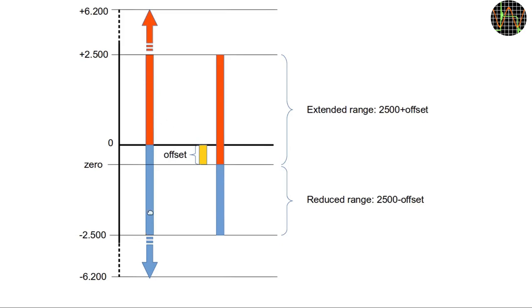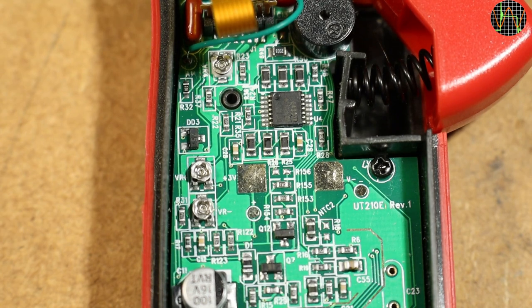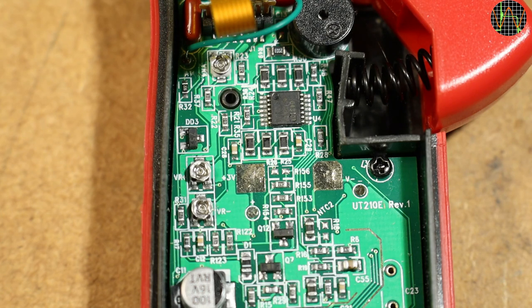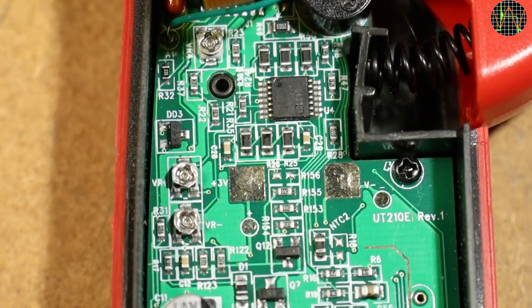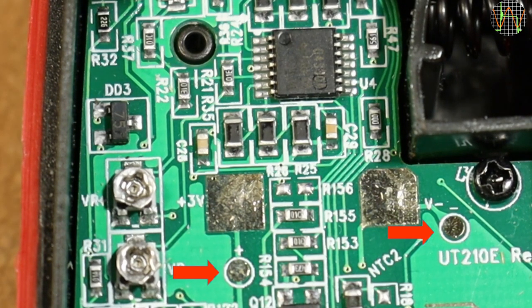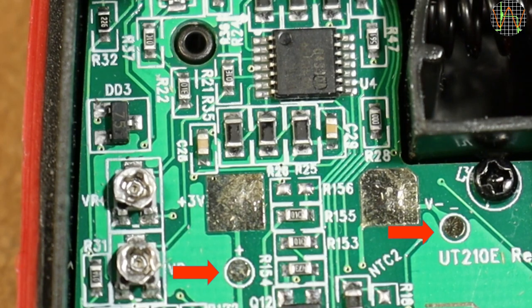So you may want to consider reducing an offset of 100mA or more by adjusting the trim pots. The first problem you have to solve is how to power the meter during the procedure. A few steps in the procedure really require the meter to be on while adjusting the trim pots, which means it has to be open so you can use the built-in battery compartment in the lid. As you can see, the meter has those square contact areas on the PCB, on which the metal springs of the battery compartment land when the back lid is closed. Next to the square areas are two round contacts and some people use these to solder wires on to temporarily power the meter when the back is off.